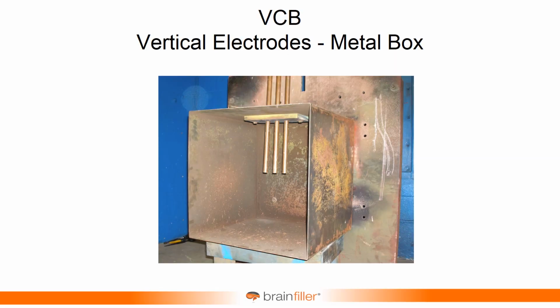Now you know. So the VCB, this is a setup that I was part of in the lab several years ago. This isn't a picture of what was done with the next edition. There are photos of the actual test setups for the next edition in the new IEEE 1584 standard. This is very typical of that kind of a setup. So you see the 3 electrodes, and you take a fuse wire, I call it a trigger wire, and wrap it around the electrodes, and that basically creates a short circuit.